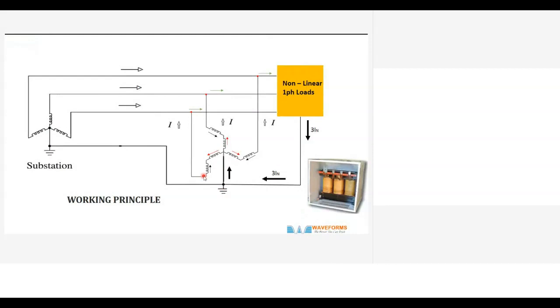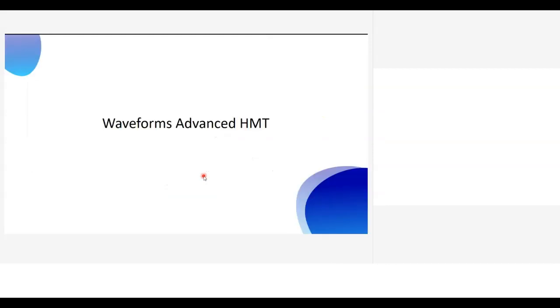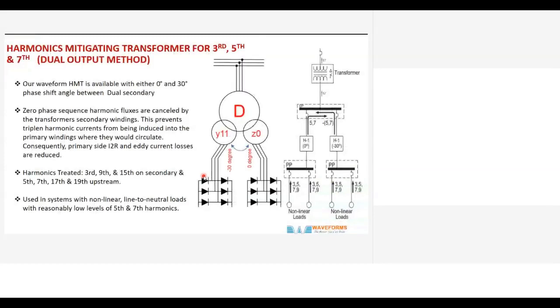And then this is a very good thing for medical centers, for testing labs, and very expensive instruments. This type of filter will be very useful in spite of having a UPS, because the voltage can still get distorted when you have third harmonic current. So this is the Waveforms Advanced Harmonic Mitigation Transformer.